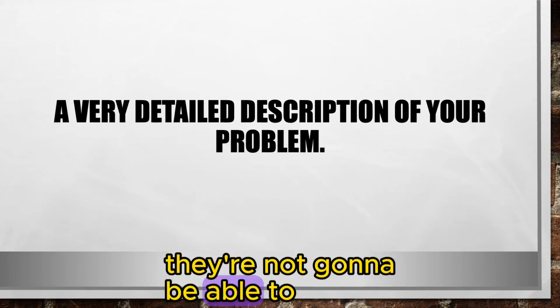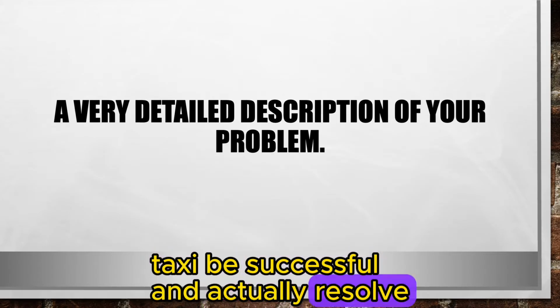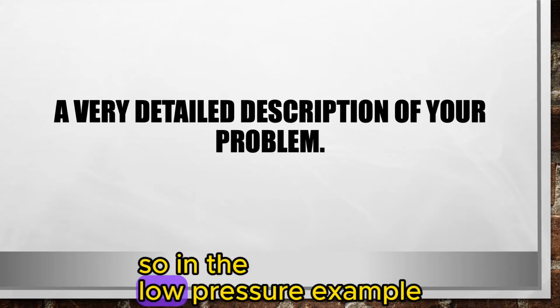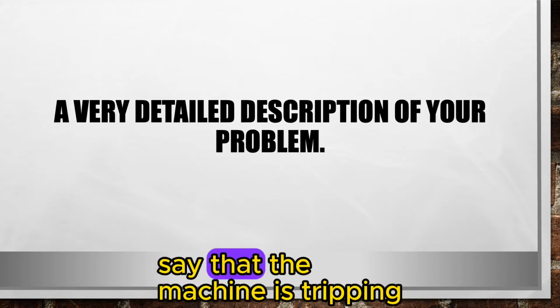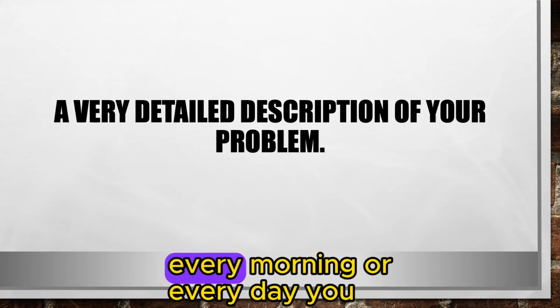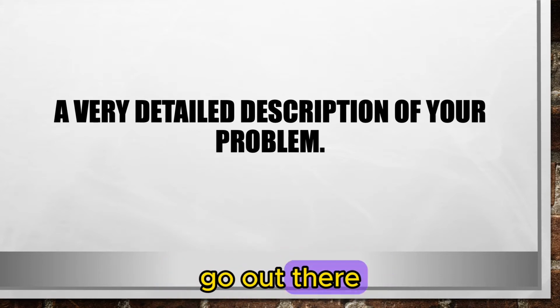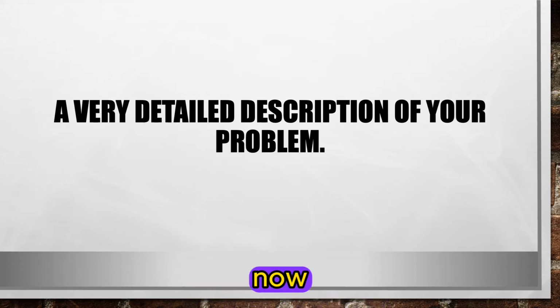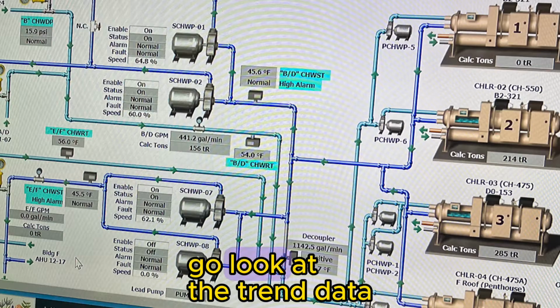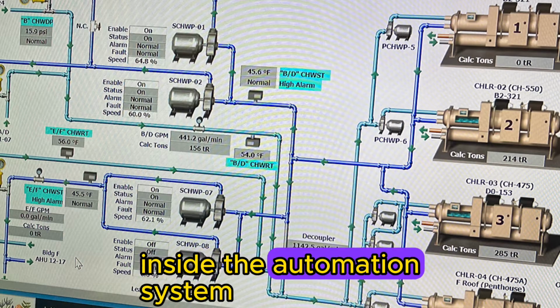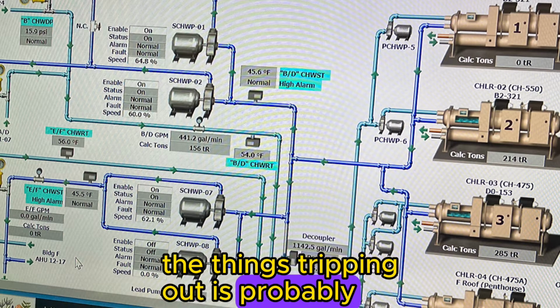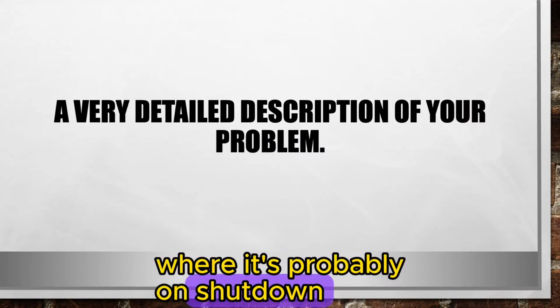Otherwise, they're not going to be able to give you the information you need to actually resolve the problem. So in the low pressure example, say the machine is tripping out on low pressure every morning, or every day you go out there it's tripping. Now that technician might be able to tell you, hey, go look at the trend data inside the automation system, it's probably tripping on startup or on shutdown.